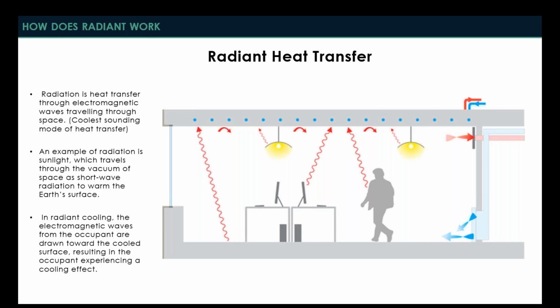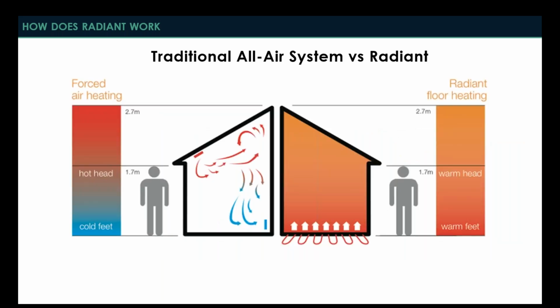In radiant cooling, electromagnetic waves from the occupant are being drawn toward the cooled surface, which results in the occupant experiencing a cooling effect. And this is sort of back to physics 101 classes, where energy travels from a high state to a lower state. It's not the radiant panel projecting cooling onto you. It's you rejecting your heat to the radiant panel, which actually creates the sense of cooling.